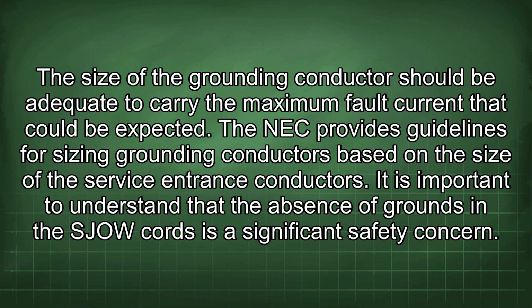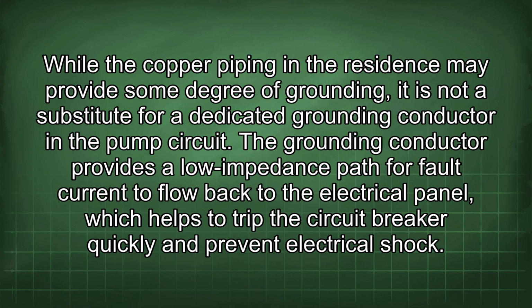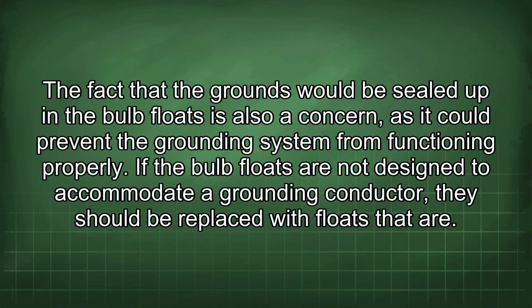It is important to understand that the absence of grounds in the SJOW cords is a significant safety concern. While the copper piping in the residence may provide some degree of grounding, it is not a substitute for a dedicated grounding conductor in the pump circuit. The grounding conductor provides a low impedance path for fault current to flow back to the electrical panel, which helps to trip the circuit breaker quickly and prevent electrical shock. The fact that the grounds would be sealed up in the bulb floats is also a concern, as it could prevent the grounding system from functioning properly. If the bulb floats are not designed to accommodate a grounding conductor, they should be replaced with floats that are.